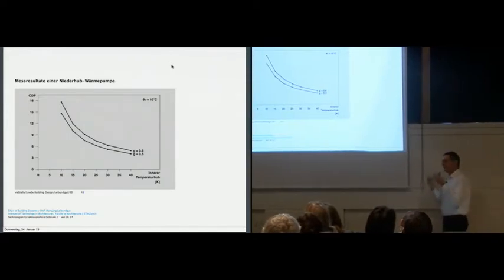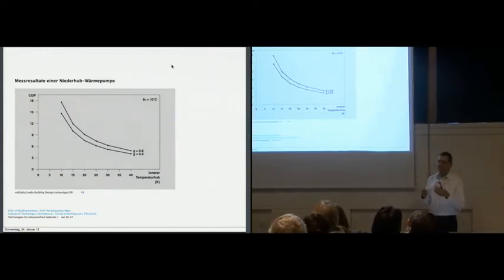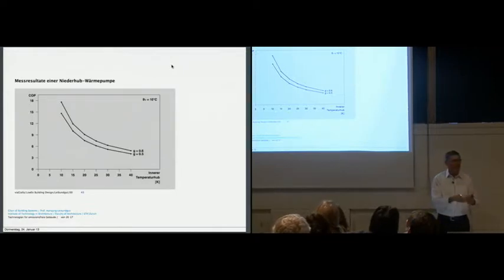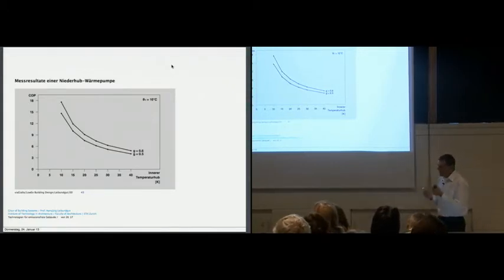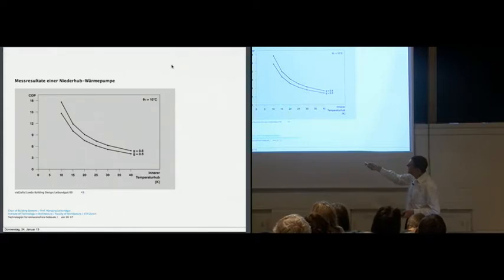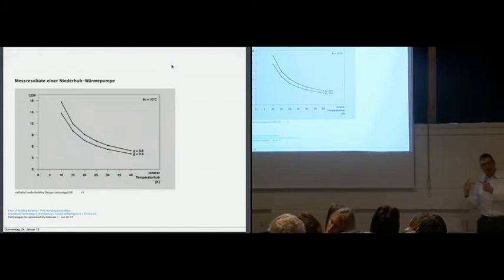You divide the temperature by a factor as the temperature difference, and if the temperature difference becomes 0, x divided by 0 is infinite. So you are like here. So what we do now, we try to establish a system with a temperature lift of about 15 to 20 degrees centigrade. That is what we want to have. And that has to do with buildings, not with a machine.